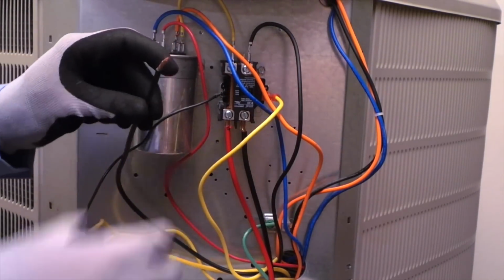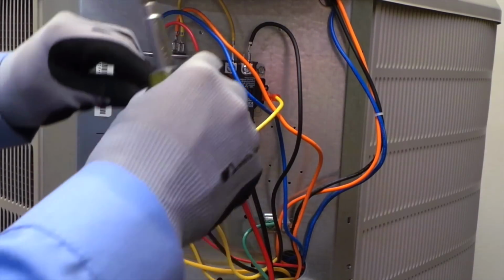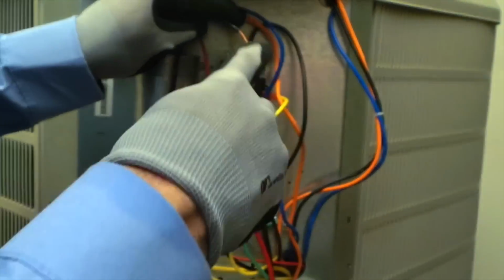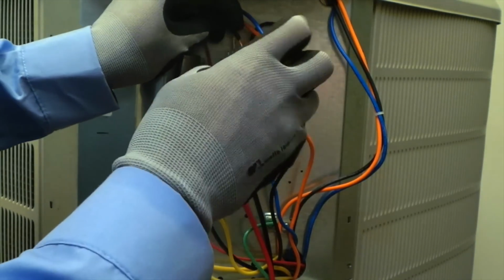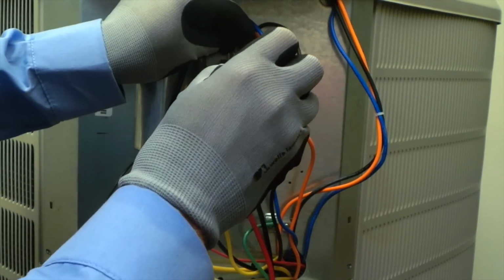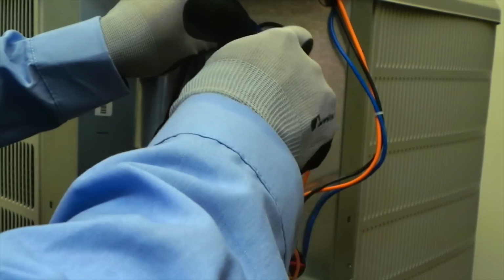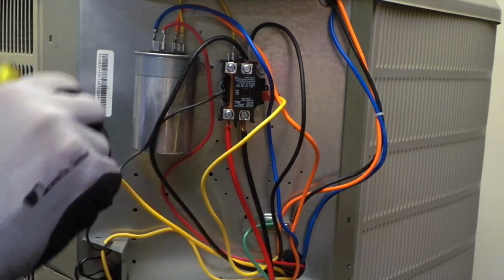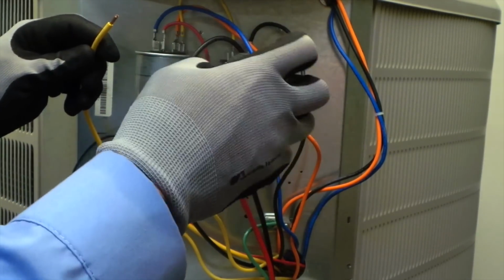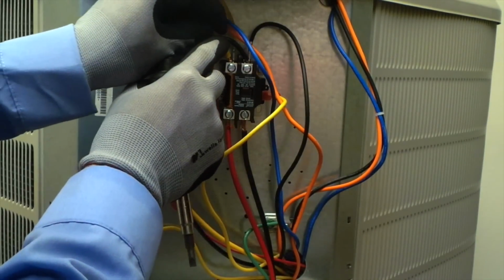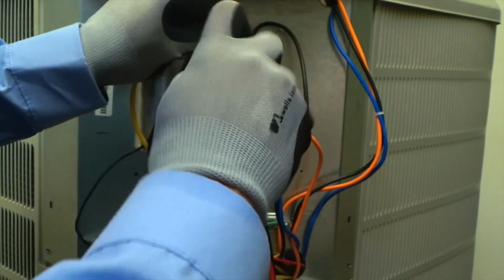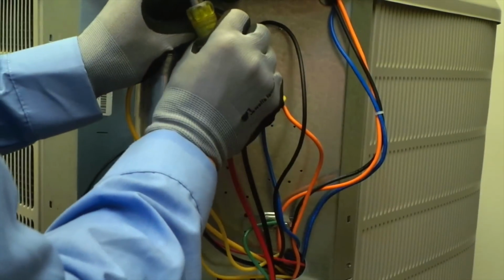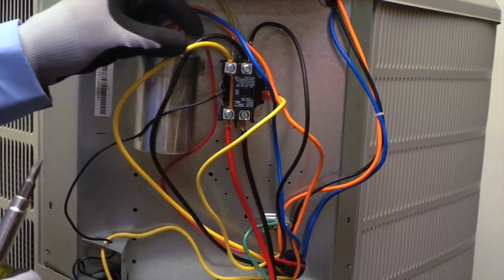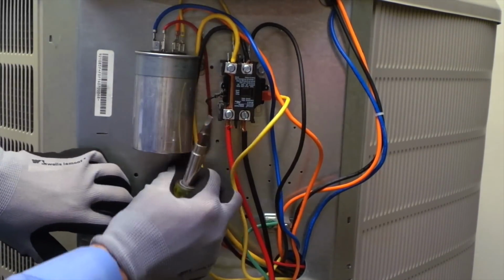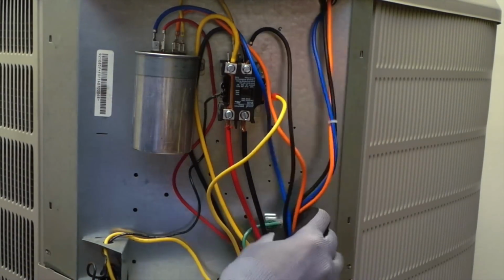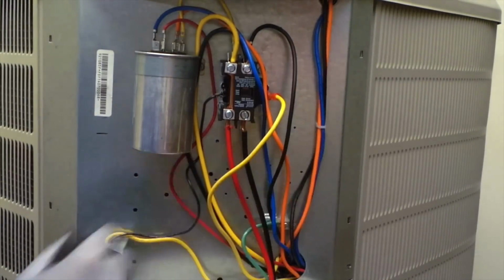Now, let's insert our wires into the lugs of our contactor. We hook our black wire to the right side of the contactor, which, remember, is the side with the contact points, as was the case with the original contactor. Then we tighten the lug down nice and tight to our new connection. Then we take the yellow wire that comes from the run terminal on our compressor, and we hook that to the left side of our contactor. That would be the shunted side. Again, making sure that all the wires go into the lug and that we have no frays. We get that nice and tight. At this point, we want to make sure that we tuck our wires into position so that we can avoid any pinch points and any possible shorts. Now, your contactor is installed.